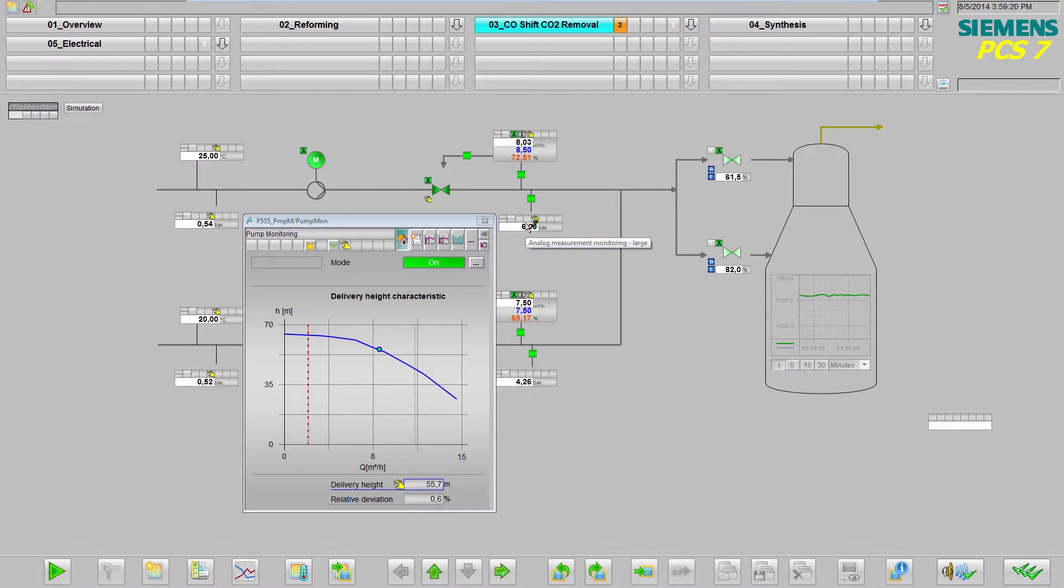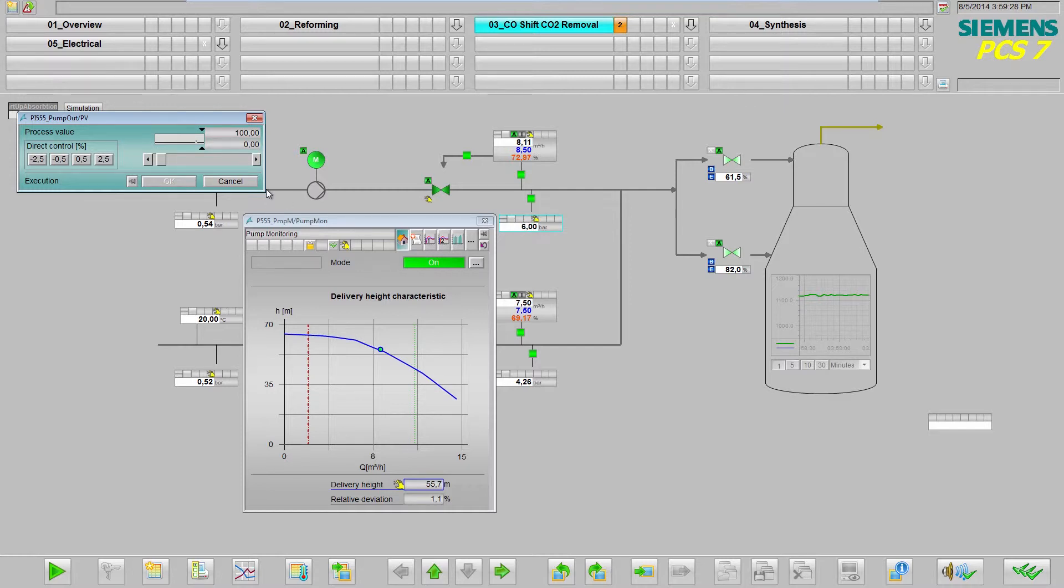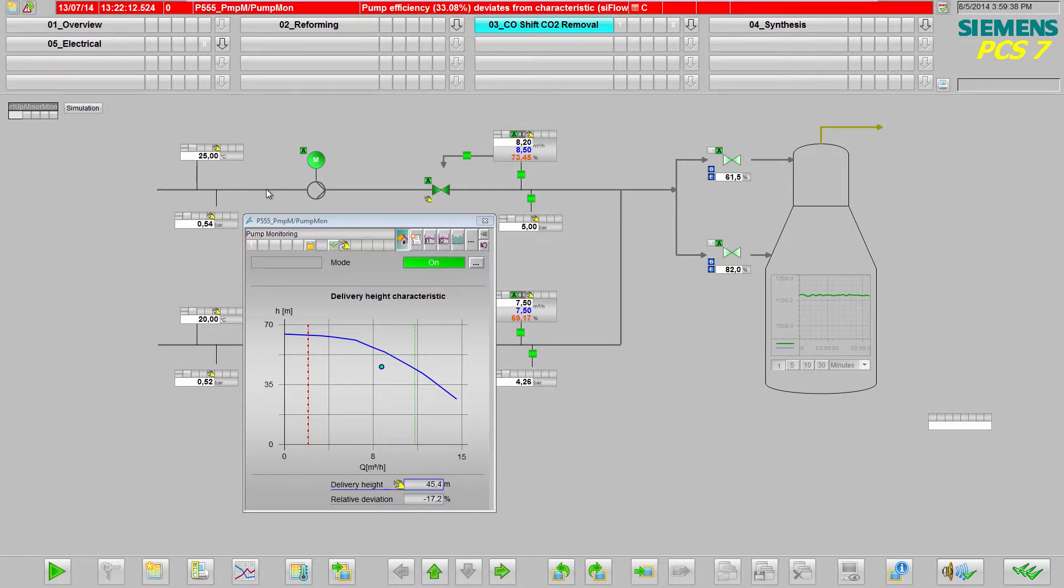I am now simulating wear to the pump in the form of a drop in the pressure on the pressure side. The wear to the pump gives rise to a deviation in respect of the characteristic curve. That means the pump is generating less pressure even though the flow is the same, and the pump efficiency is also dropping due to this wear.